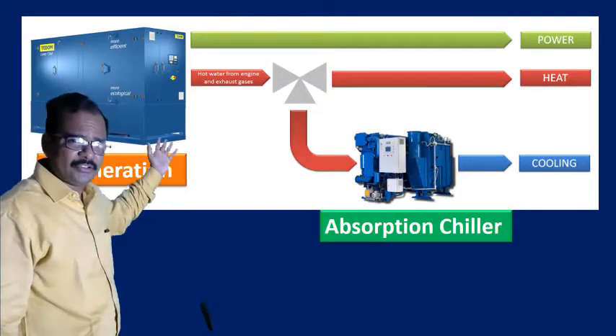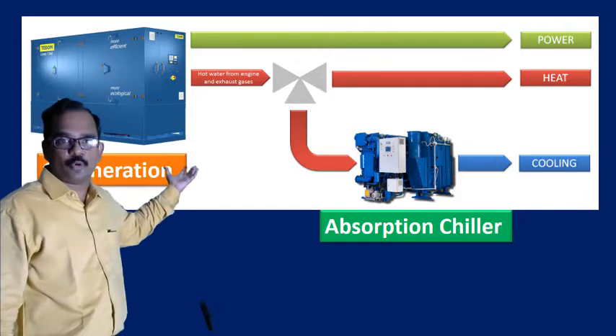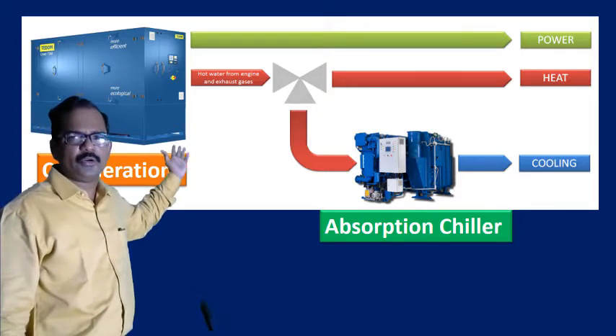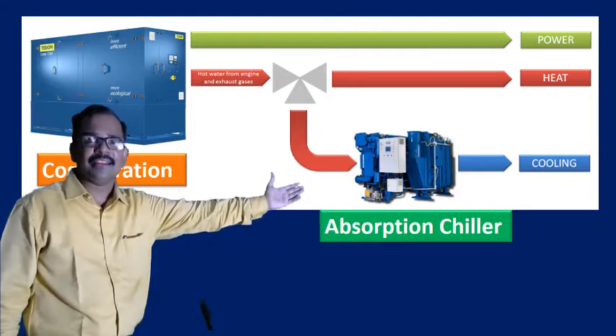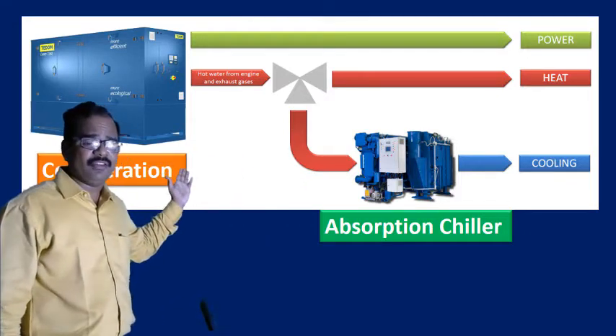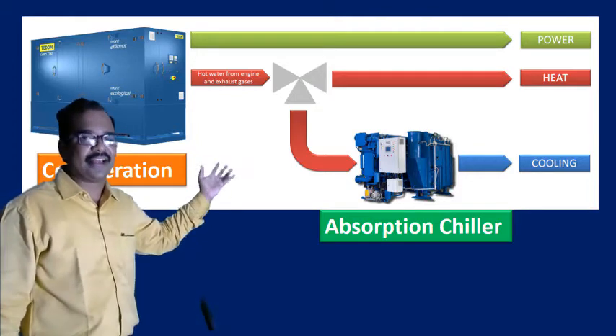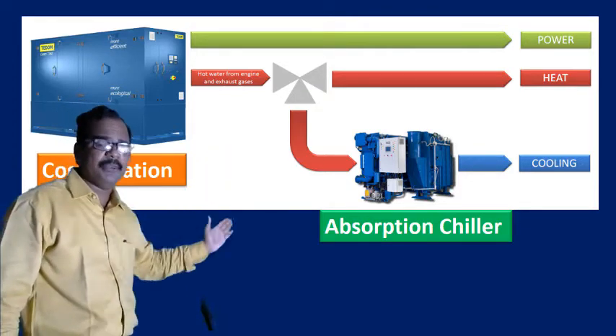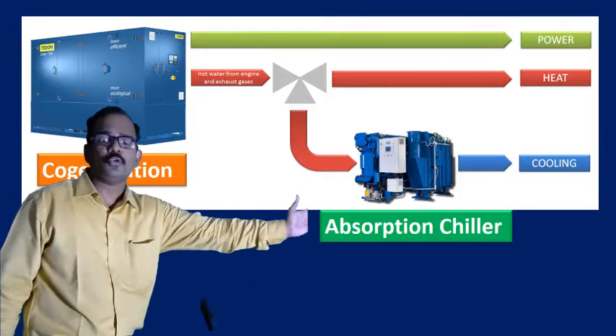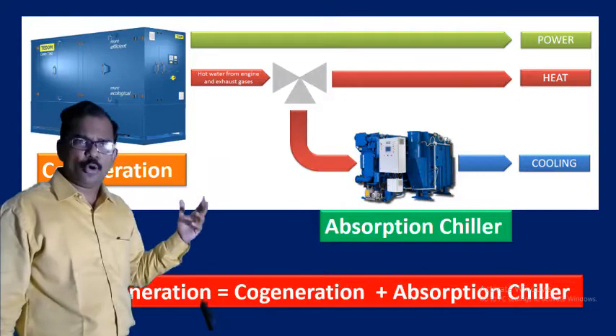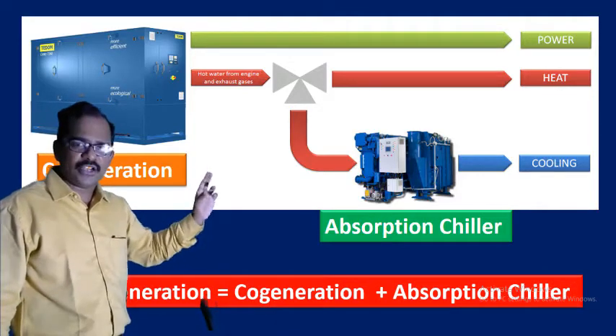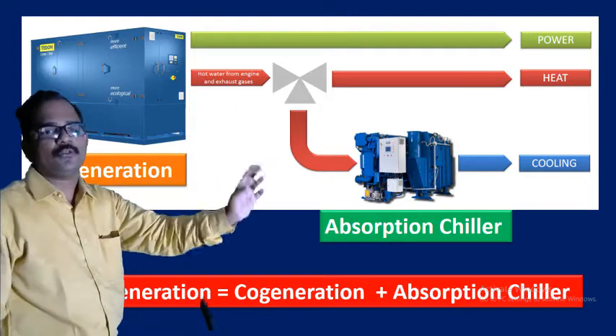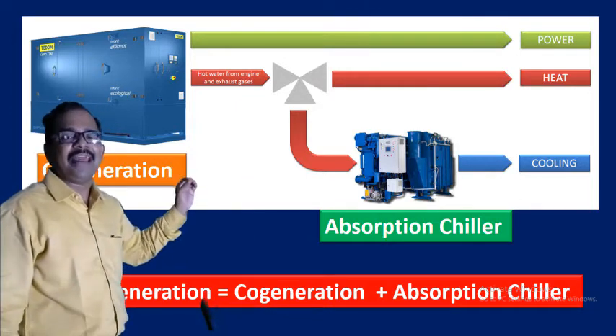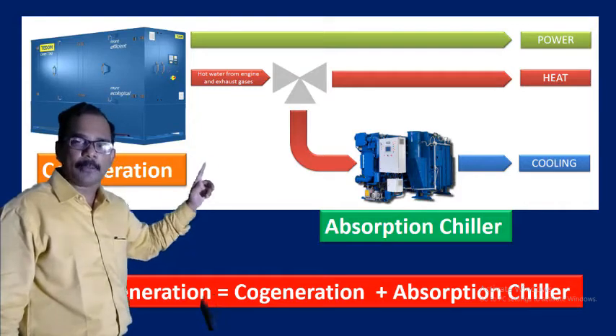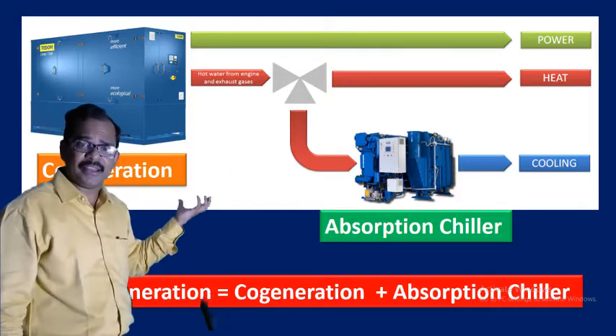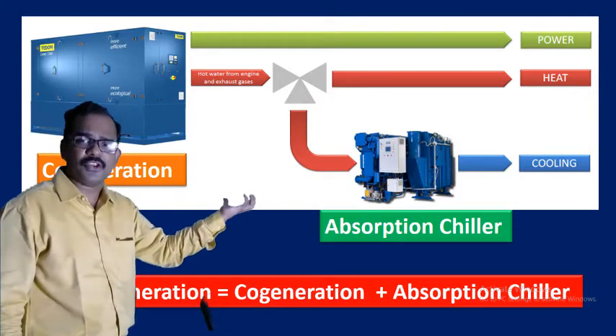As you can see here, there is a cogeneration technology, which you can see in the slides over here. This cogeneration means if I give a fuel to it, I will get the power and heat. And the engine will produce some exhaust gases, and that exhaust gas will be used in the absorption chiller for getting the cooling. Right. So, on the whole, the trigeneration is nothing but a cogeneration plus an absorption chiller. So, we can convert a cogeneration system by adding an additional equipment called an absorption chiller. So, a trigeneration is nothing but a combination of cogeneration and absorption chiller.